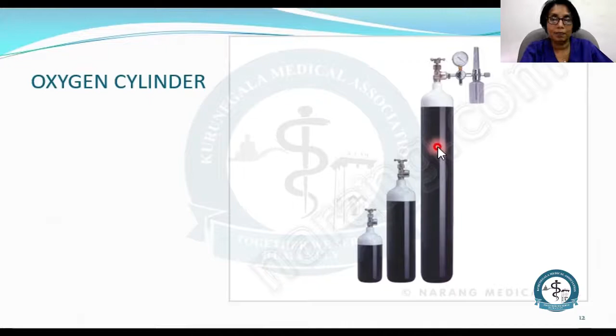How do you calculate the oxygen content of a cylinder? Oxygen content of a cylinder is equivalent to the cylinder volume multiplied by the cylinder pressure. In a jumbo cylinder, there is a volume of 47 liters and its oxygen is stored under a pressure of 137 bars. So it contains 7,200 liters of oxygen. If you take a type D cylinder, those are the types of cylinders you find in wards. It has a volume of 10 liters and it contains 1,400 liters of oxygen. Type E cylinders, these are the cylinders you find in anesthetic machines, contain 720 liters of oxygen.